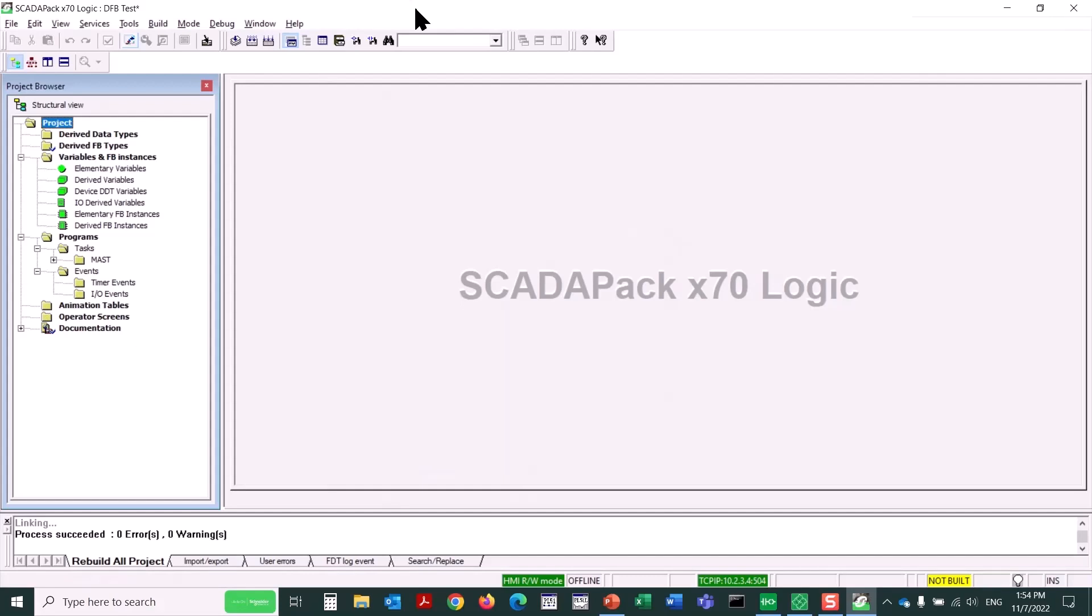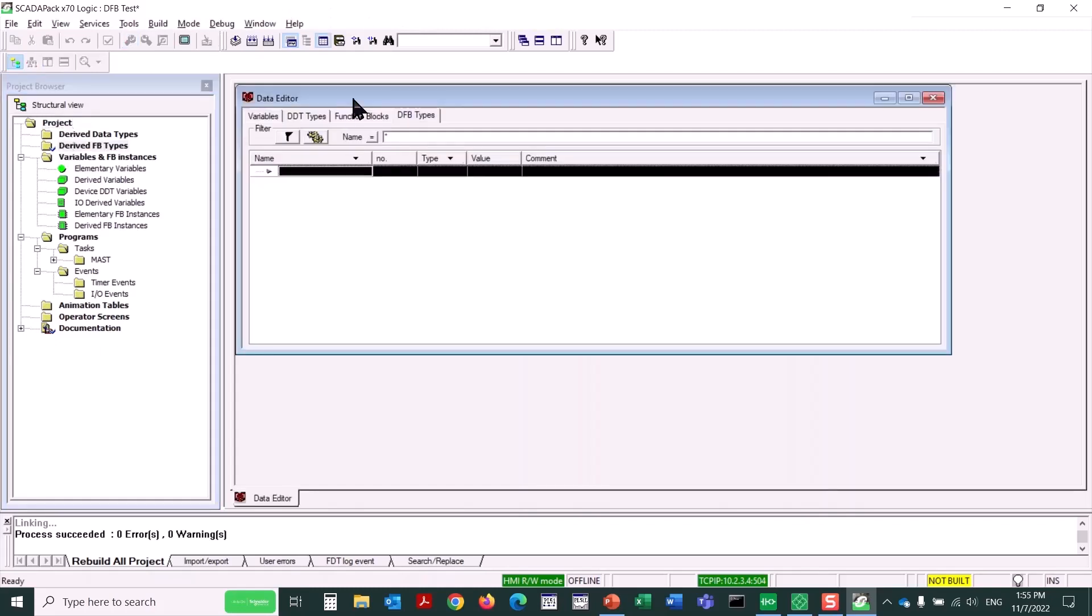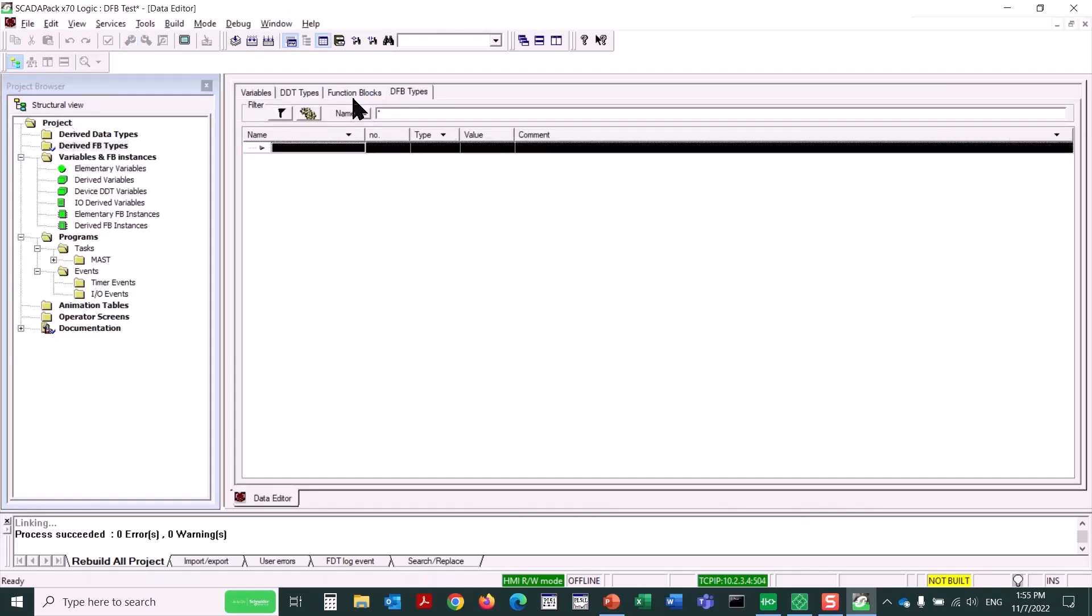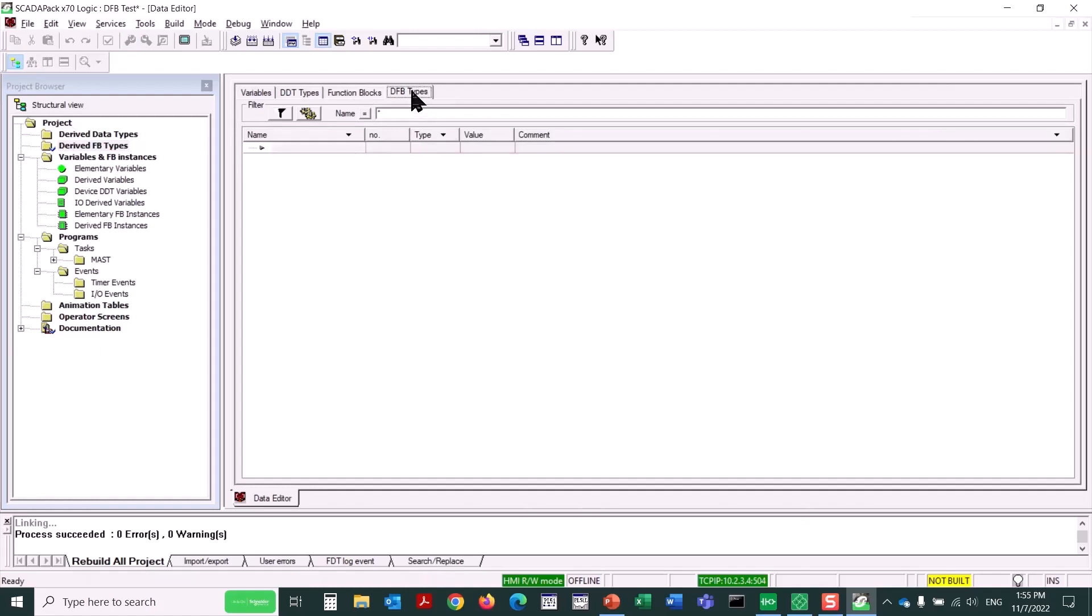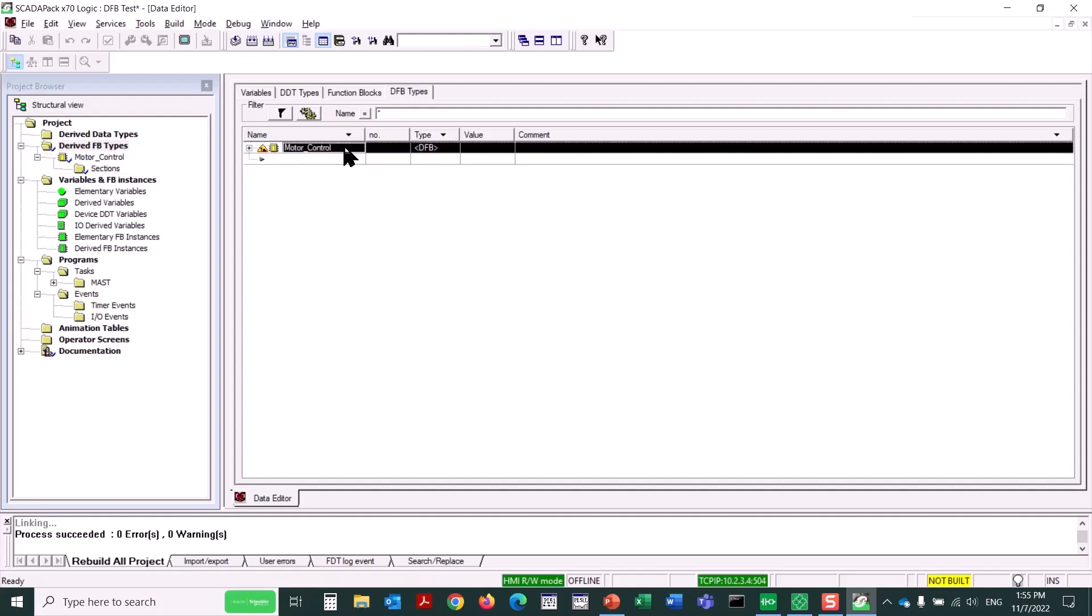So now that I've got the Remote Connect application ready to go, I've opened SCADAPack Logic Editor, and to start creating a derived function block, I'm going to double-click on the derived FB Types folder. We make sure that DFB Types is selected here. Now I'll click on the first available line, and give this derived function block a name. I'll call it Motor Control, simply enough.